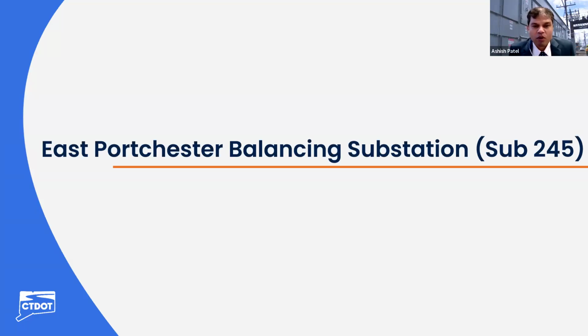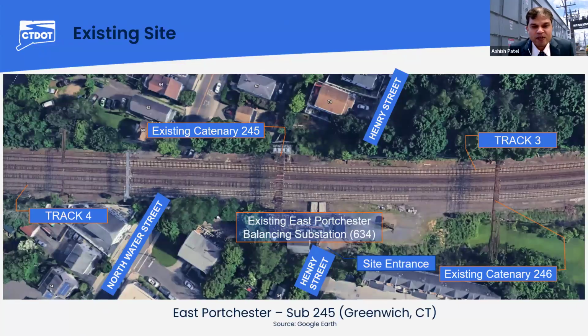I will give a brief overview of the replacement of Site 2 East Portchester balancing substation scope of work. The existing East Portchester balancing substation is located at East Portchester, adjacent to Henry Street in the town of Greenwich, Connecticut. As we can see on this Google image, the New Haven main line 4 tracks are shown on the north. The existing East Portchester balancing substation is located on the south side of Railroad Track 4 and at the end of Henry Street. The project site entrance is from Henry Street, located on the south side of the New Haven main line. The portion of driveway is shared by residents of Greenwich and the railroad personnel. So again, it is critical to respect each other during the construction phase. There are many residential houses, apartments, and a commercial building located adjacent to the proposed site.